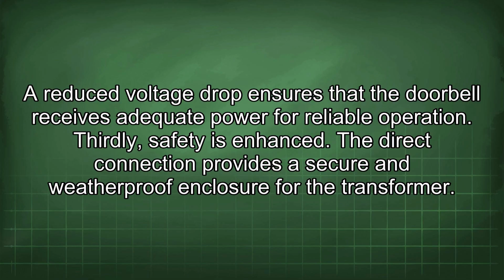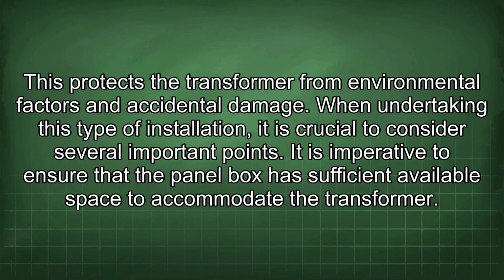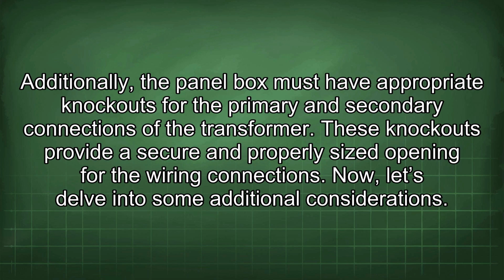Thirdly, safety is enhanced. The direct connection provides a secure and weatherproof enclosure for the transformer. This protects the transformer from environmental factors and accidental damage. When undertaking this type of installation, it is crucial to consider several important points. It is imperative to ensure that the panel box has sufficient available space to accommodate the transformer. Additionally, the panel box must have appropriate knockouts for the primary and secondary connections of the transformer. These knockouts provide a secure and properly sized opening for the wiring connections.